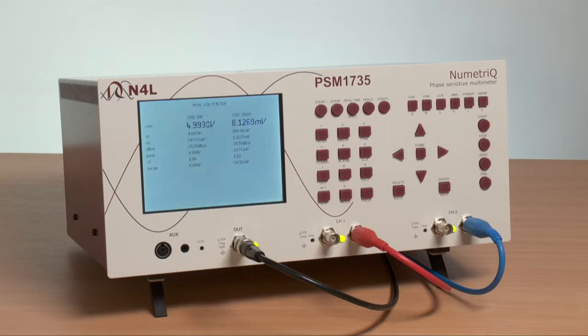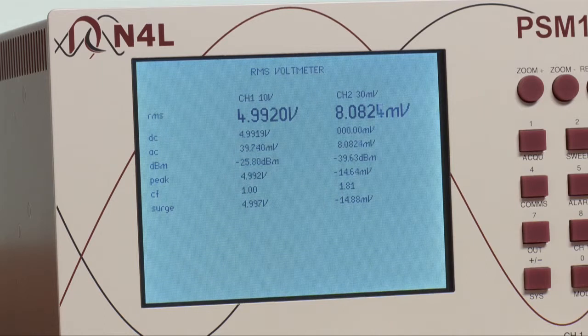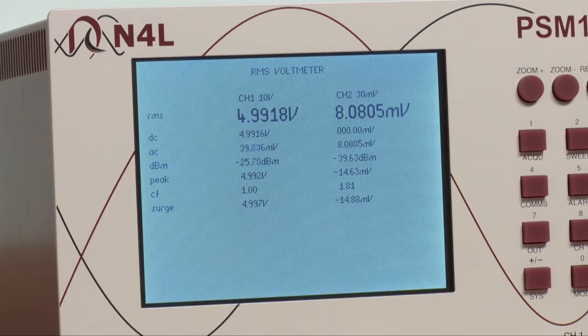The PSM 1735 is a true wideband RMS instrument, so we have AC, DC, dBm peak, crest factor, and surge measured for both channels. The channels can be voltage measurements, which is the default mode, or become current by virtue of shunts for different applications. In this case, however, we are just looking at voltage.